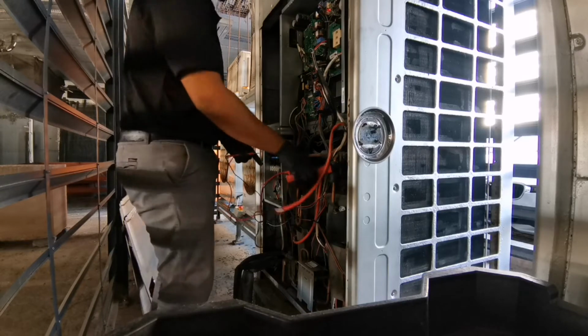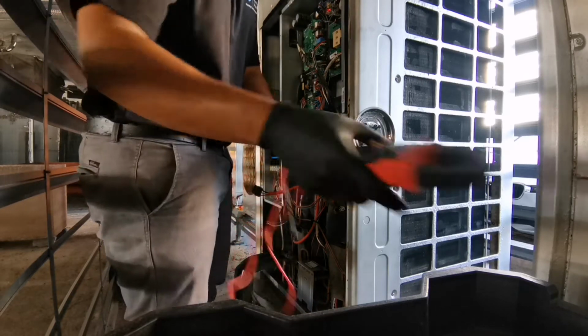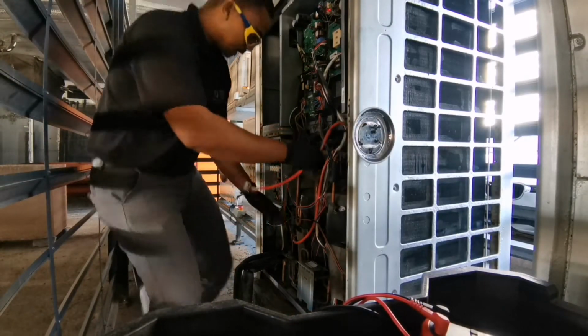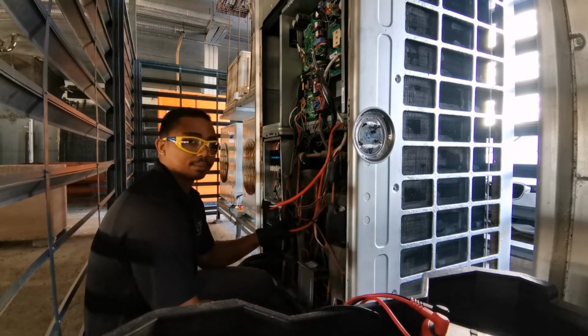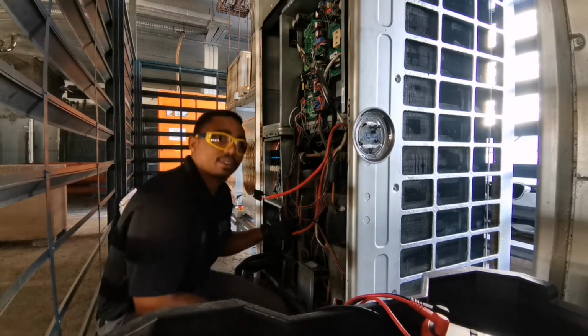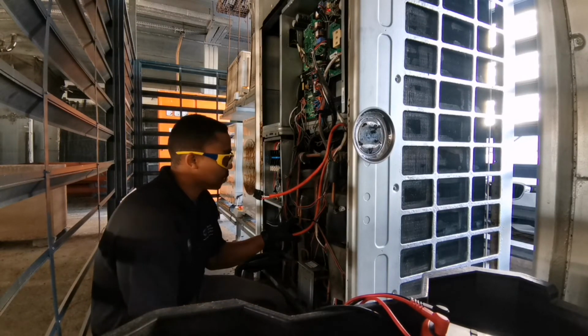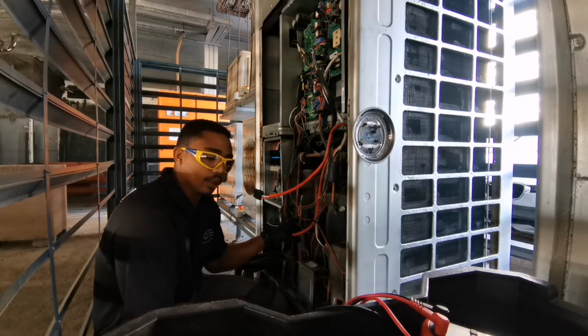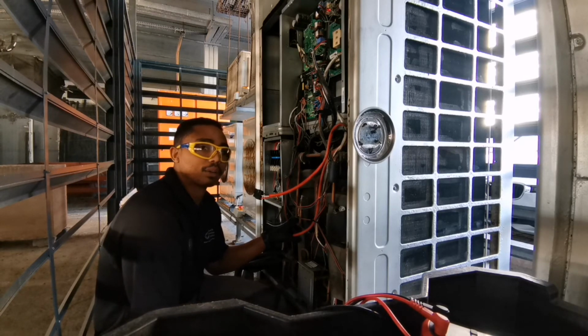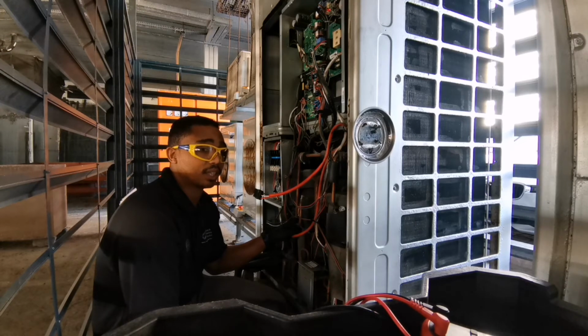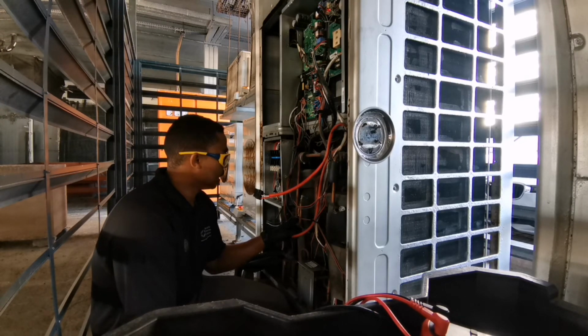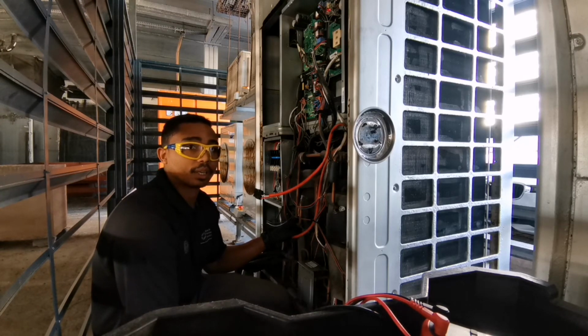So we definitely got a grounded compressor, and that will be this one. Now, when you're working on VRF systems, the thing that you want to consider is the oil contamination. So now we know that we've got a grounded compressor, which means the insulation of our windings is being compromised. So our oil therefore is also contaminated and compromised.